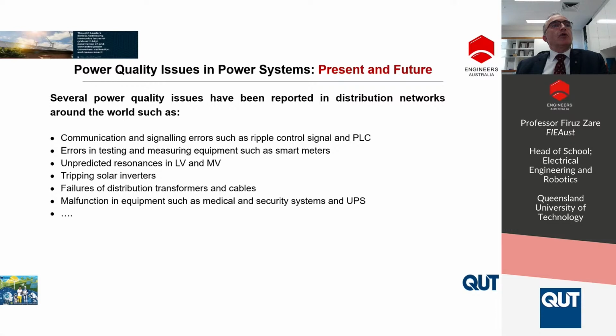And we have also seen some resonances in low voltage and medium voltage, tripping the network and tripping solar inverters, especially in residential areas or wind farms. And I have seen severe resonances and failure in cables of wind farms and some reports for the transformer and many other sensitive devices because of high frequency. I have reports from my colleagues and from industry that I'm allowed to share in the next slides.